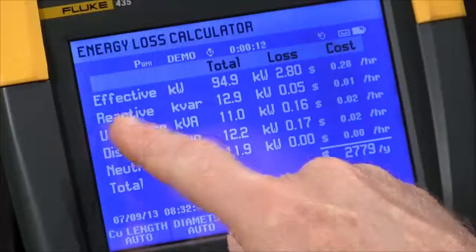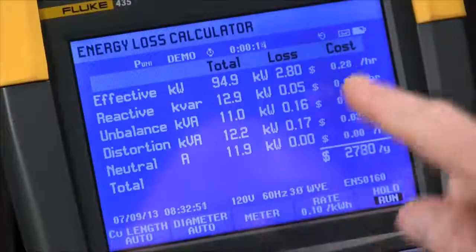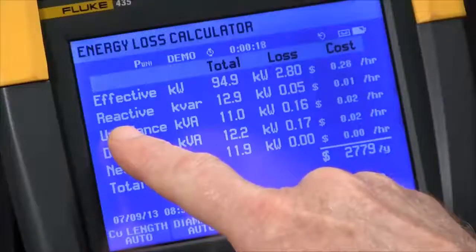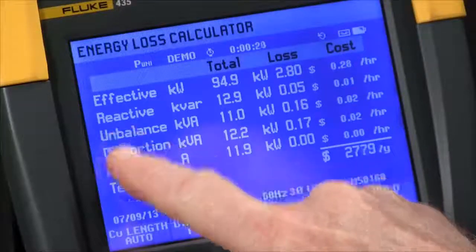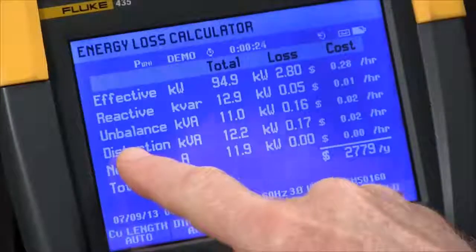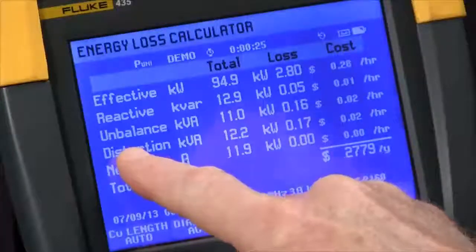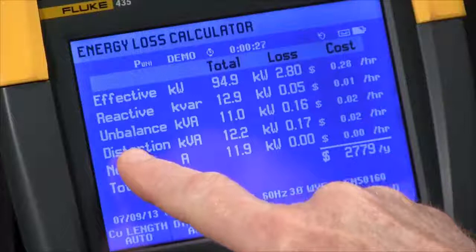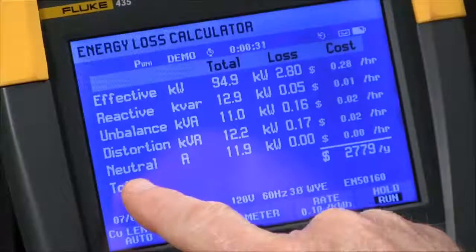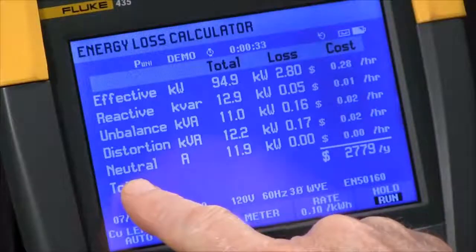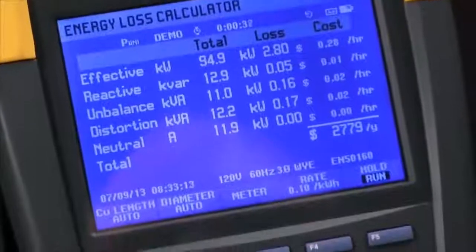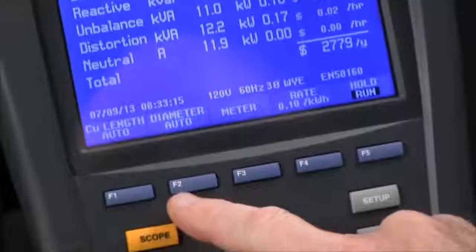Your effective power — you'll have losses due to wire resistance, and you'll see a cost per hour displayed. Reactive power might be caused by motors and capacitors in your system. Unbalance is system unbalance in terms of not being properly balanced between all three phases. Distortion would be harmonics, and the neutral losses or current flow in the neutral.